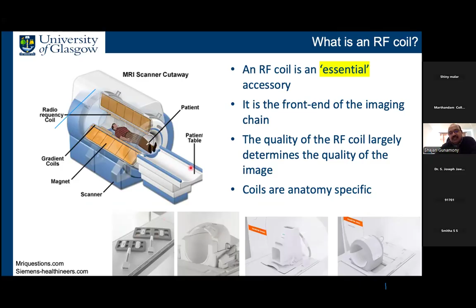And coils are made of resonance circuits. So this is the simplest form of a resonance circuit, where you have an inductor and a capacitor in parallel, and there's also a small resistance. And the coils, these resonance circuits, are tuned to the Larmor frequency, and this Larmor frequency is basically a function of the gyromagnetic ratio, that is the precession frequency of the atomic nuclei, and the main magnetic field. So if you have a 1 Tesla scanner, then for the hydrogen proton, the resonance frequency would be 42.58 megahertz.